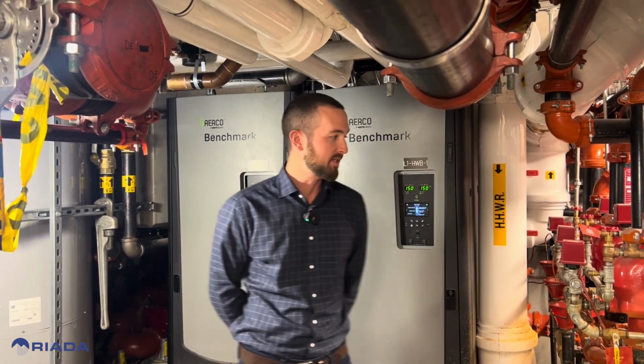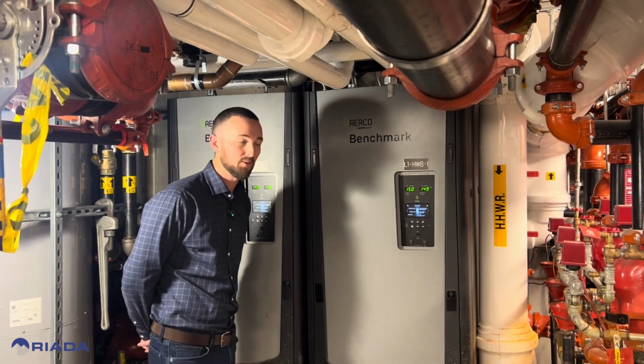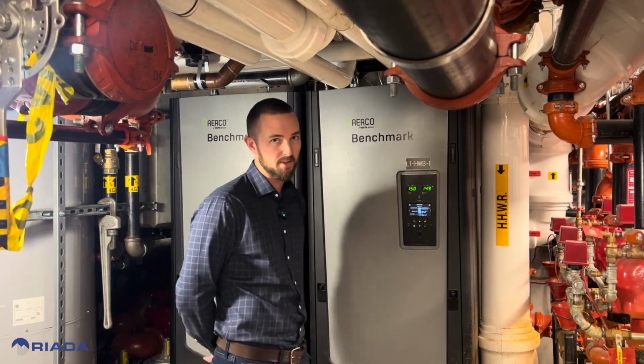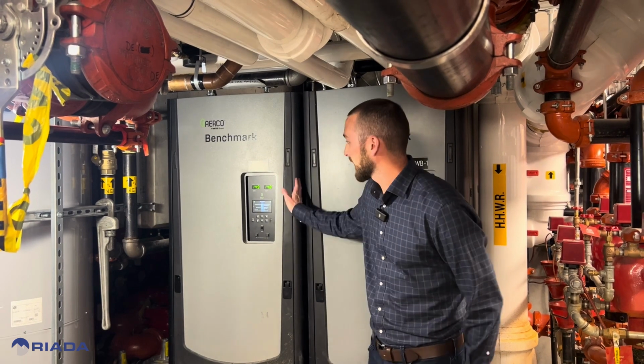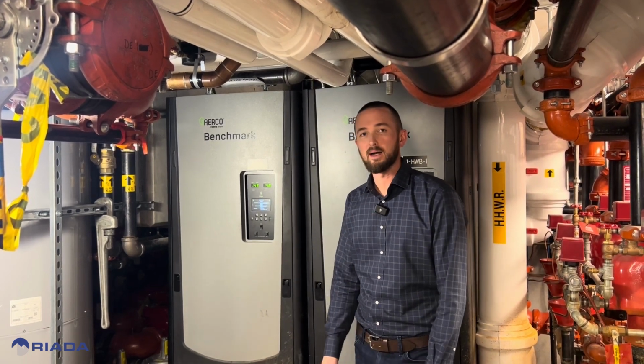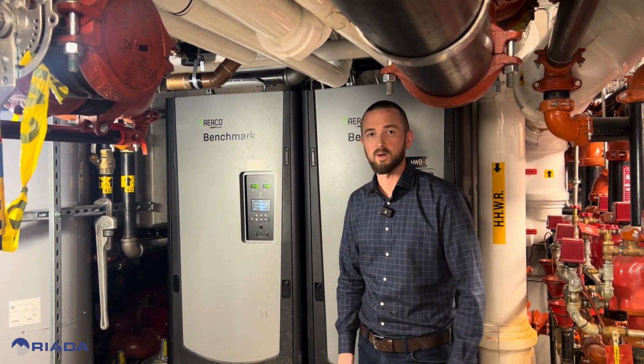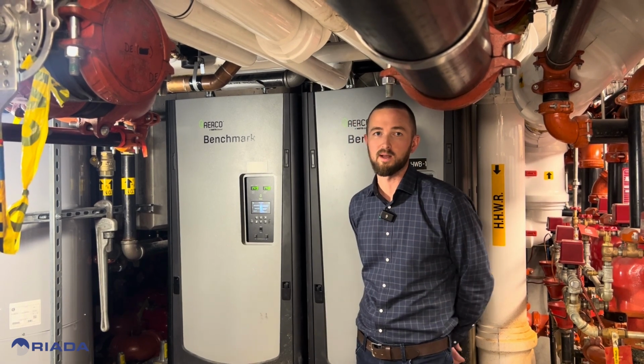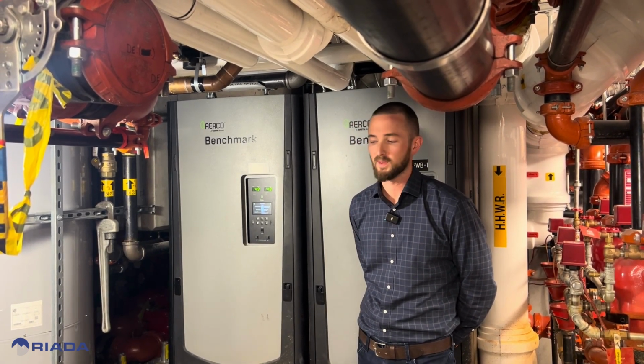We are in Richmond, BC today with a couple of AERCO Benchmark series condensing boilers behind me. These are 2 million BTUs each, and you can see how tight of a footprint they sit in this mechanical room. Luckily, because this is a very tight mechanical room with zero side clearance for servicing and a very small footprint, we're able to get 4 million BTUs here of heat output in a very small space.